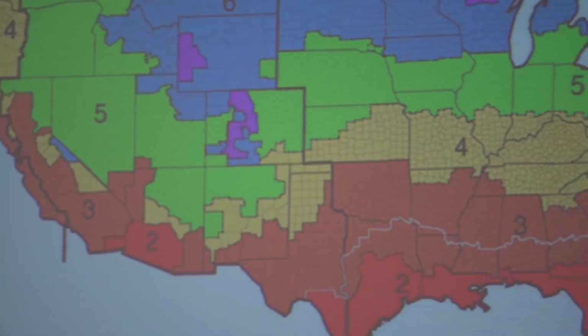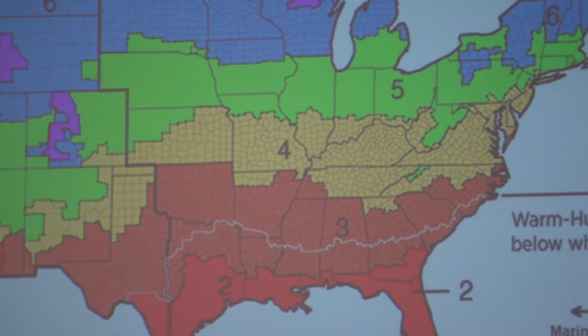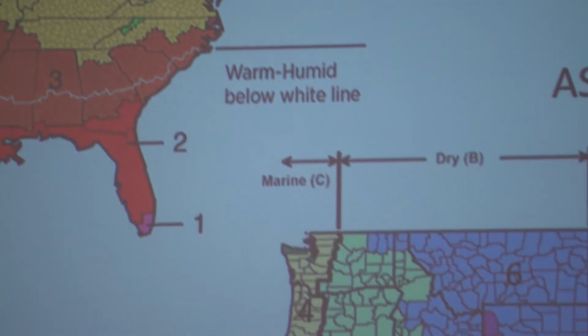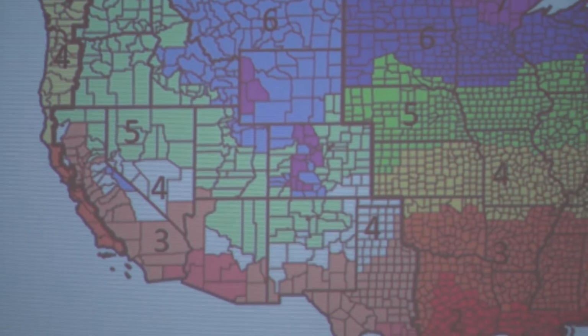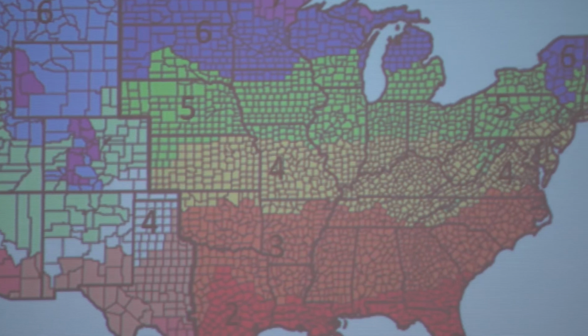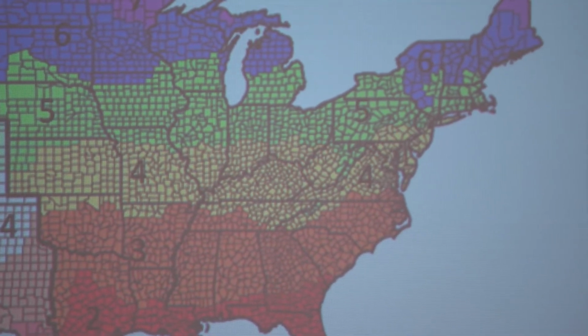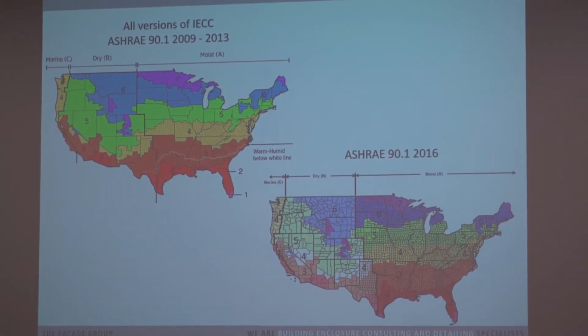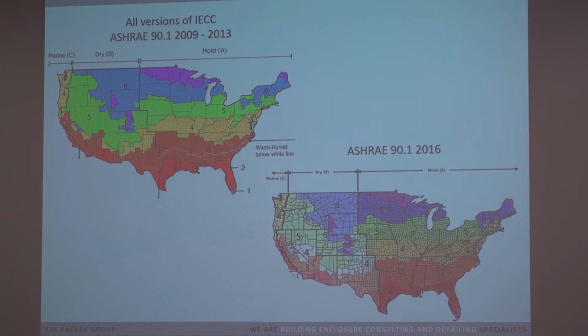But if you look at the new map for 2016, you'll see it's going to start to dip a little bit higher into Pennsylvania. I'm going to zoom in on Pennsylvania in a minute just so you can see which counties have specifically changed. But the overall trend is that lines are moving upward and reflecting that temperatures are getting warmer. And they actually even added a new climate zone. It's not on this map, but it's a zone 0 reflecting even warmer temperatures. And so the climate zones affect the envelope probably the most of any of the sections. And what does that mean? It sort of means that if you're moving to a lower climate zone, well, you sort of need less insulation, except at the same time, building codes are increasing insulation.